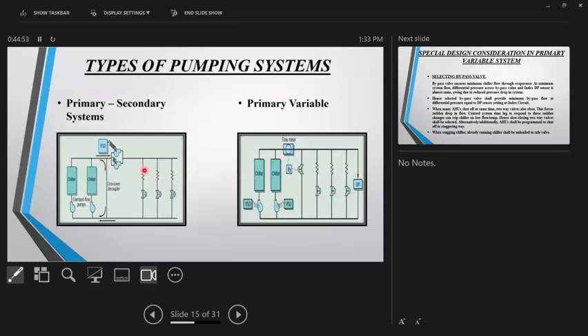Types of pumping system, I think there's not much need to spend time on this. In the primary secondary systems, you have a set of a production loop with usually constant flow pumps. You have a bypass or decoupler line. You have a set of secondary pumps which get speed regulated with a differential pressure transmitter, which is not shown here, but it's the same theory which we spoke about.